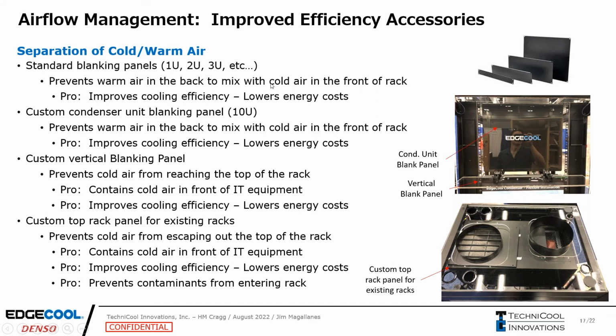Everybody knows about standard blanking panels, 1U, 2U. We want to keep those in the rack to prevent mixing of the warm air and the cold air. If the condenser unit is installed inside the rack, we also can put in an acrylic panel there to prevent, again, warm air from mixing with cold air. We also have a vertical panel right below that, so the cold air coming from the bottom of the evaporator unit stays in front of the IT equipment instead of going up into the top of the rack. And if you're going into an existing server rack and putting the condenser unit inside the rack itself, you'll want to put some type of panel on top. This shows an acrylic panel that just mounts on top, very simple to install.